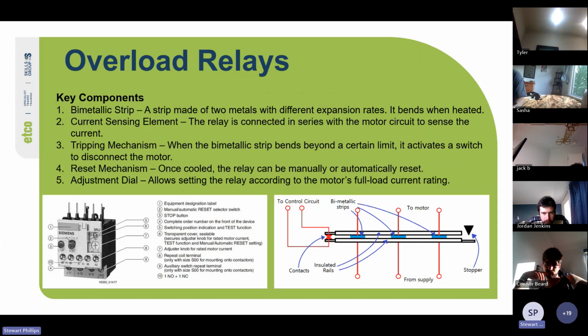Cool. So your key components. You've got your bimetallic strip, a strip made of two metals with different expansion rates. It bends when heated. The current sensing element: the relay is connected in series with the motor circuit to sense the current. Your trip mechanism: when the bimetallic strip bends beyond a certain limit, it activates a switch to disconnect the motor. Reset mechanism: once tripped, the relay can be manually or automatically reset. And then you've got an adjustment dial, which allows setting the relay according to the motor's full load rating.